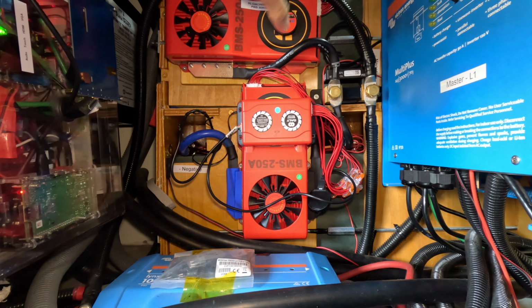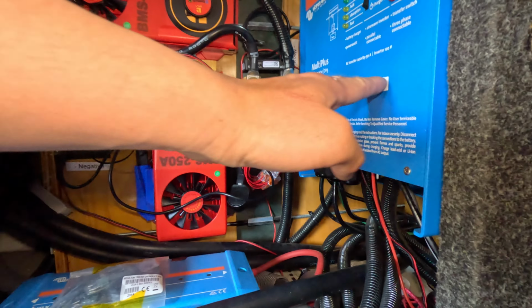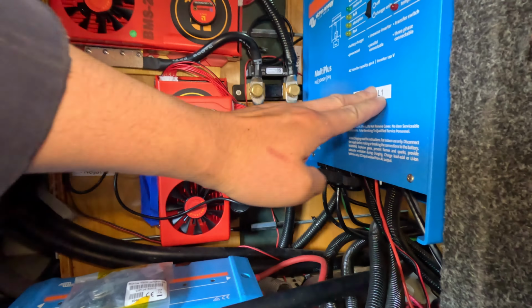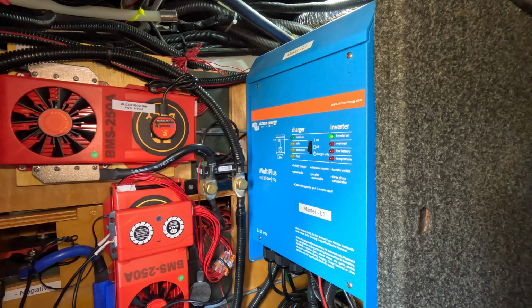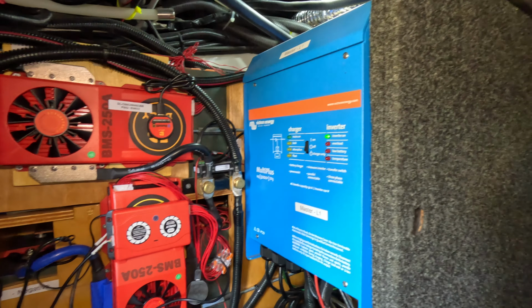Back to the AC side again, we've got power distribution from the Lynx distributor, and then it feeds to the multi-plus here, two of the multi-plus, one here, one in the back there we just saw. And then from those two multi-pluses, we've got both legs of AC coming from two of the inverters, so they are set up to be 120 and 240 setup. Each of the multi-plus feeds one leg of the distribution panel on the inside, and that runs absolutely everything, including water heaters, microwaves, induction, stovetop, and everything.